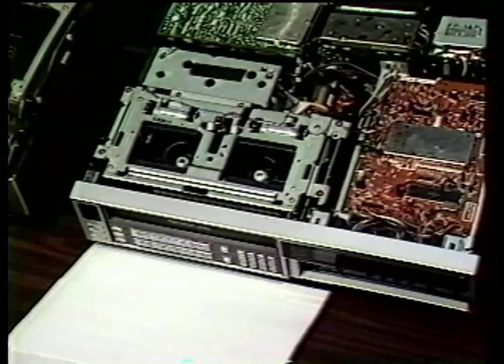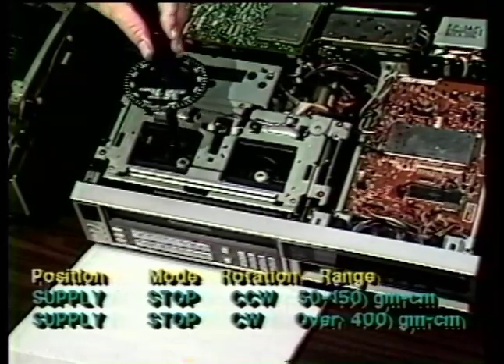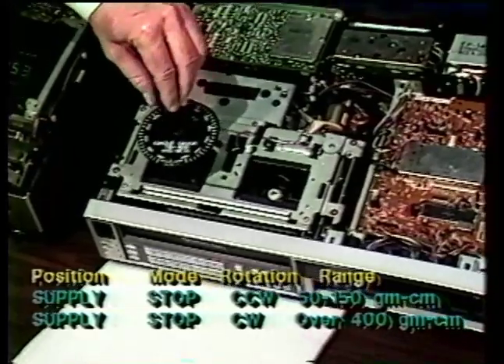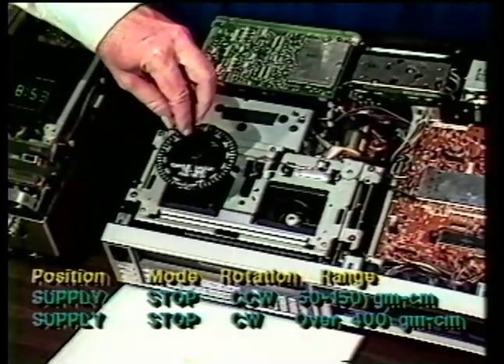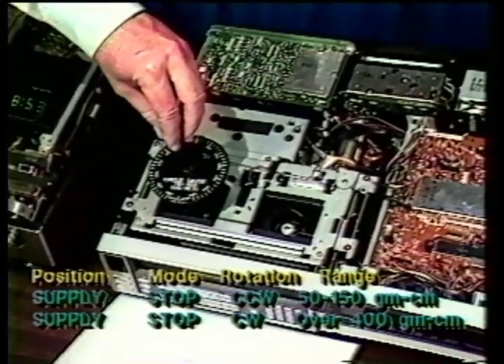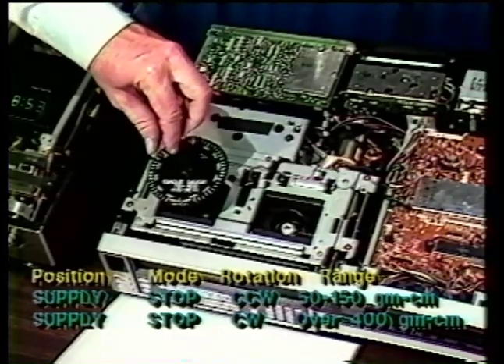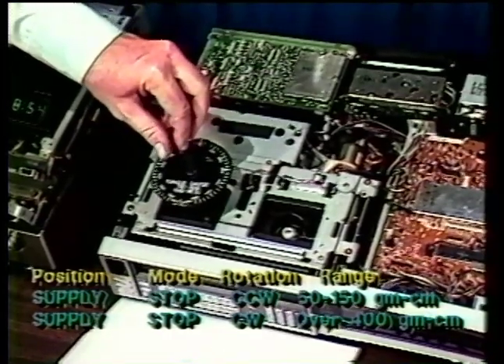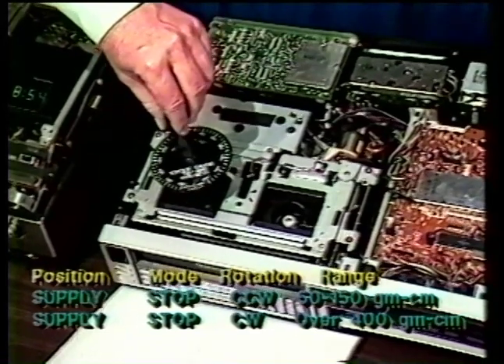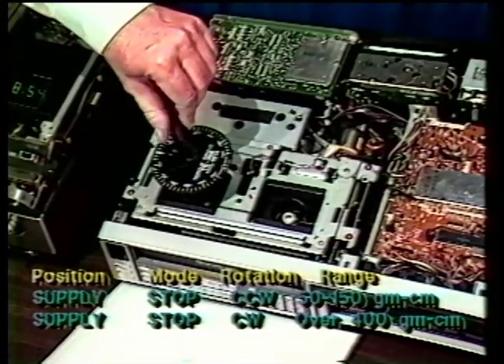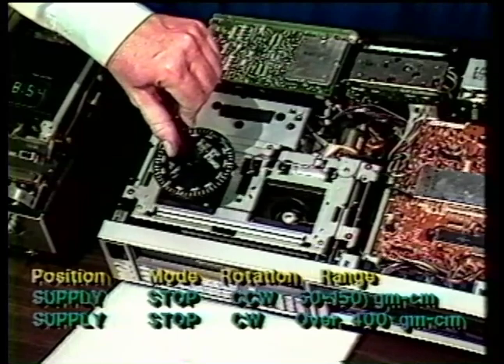With the machine in the stop mode, by placing the torque gauge on the supply spindle, we'll get one reading, and this is for a typical machine again. Look in the service manuals if it varies much from these readings. In the counterclockwise direction, it should read approximately 50 to 150 gram centimeters. You can see this is reading about 125.